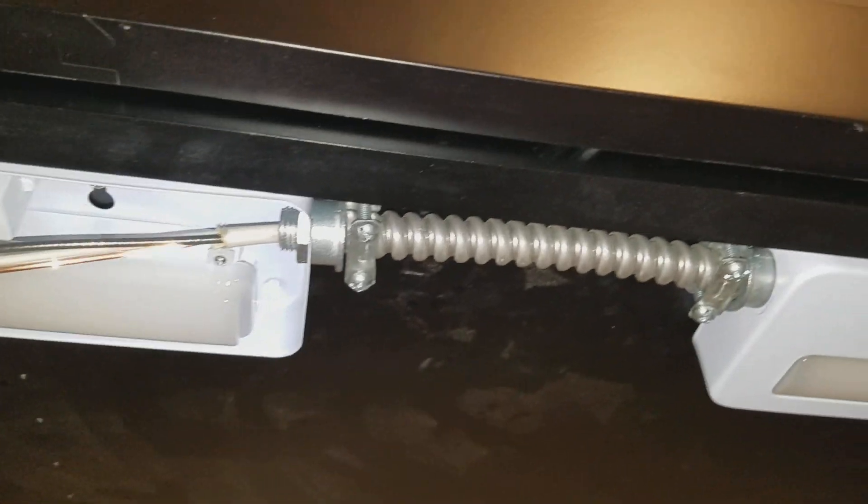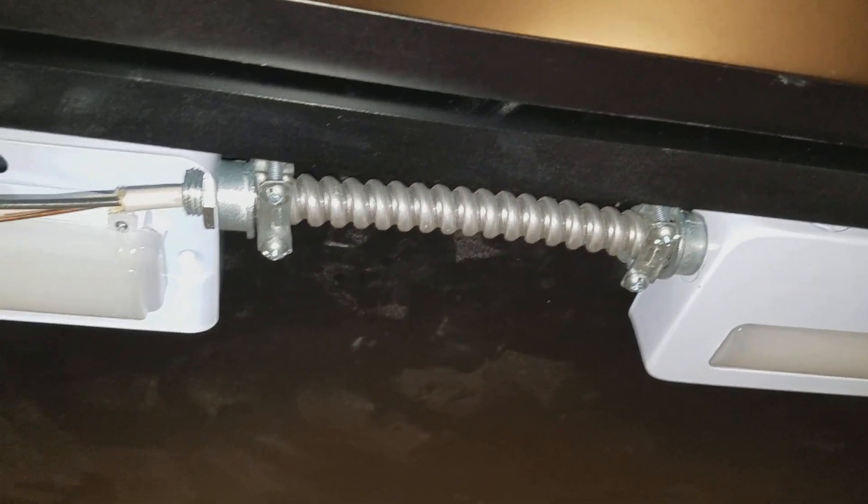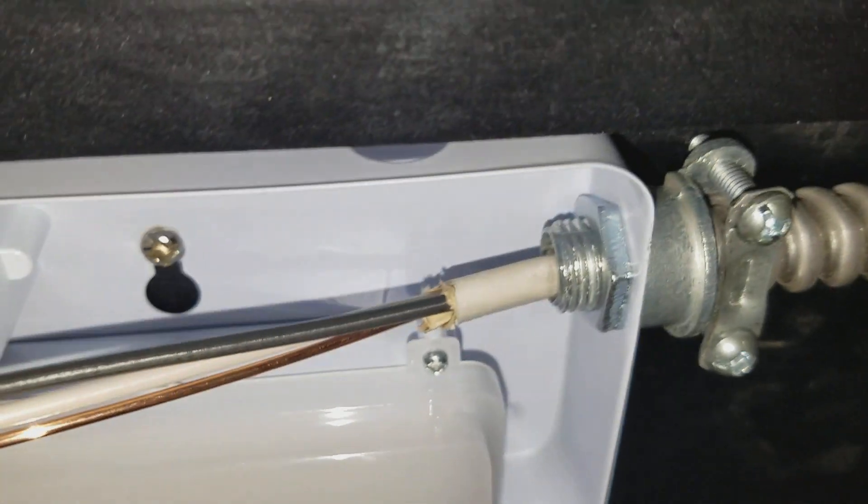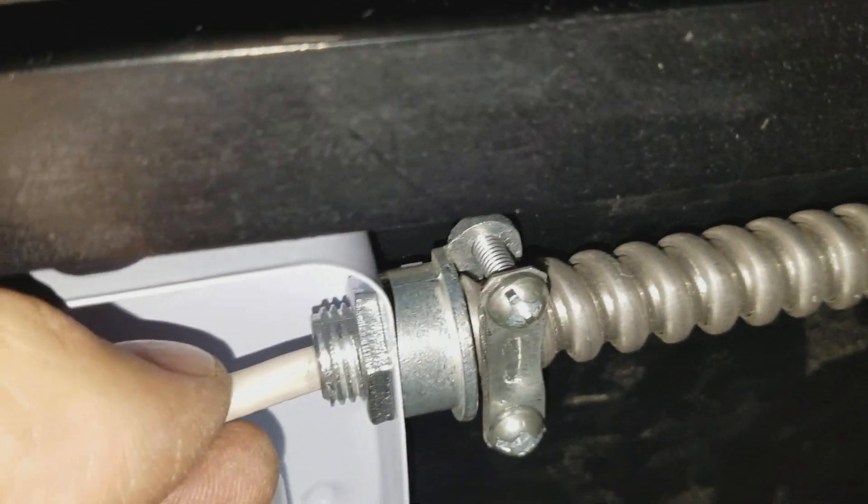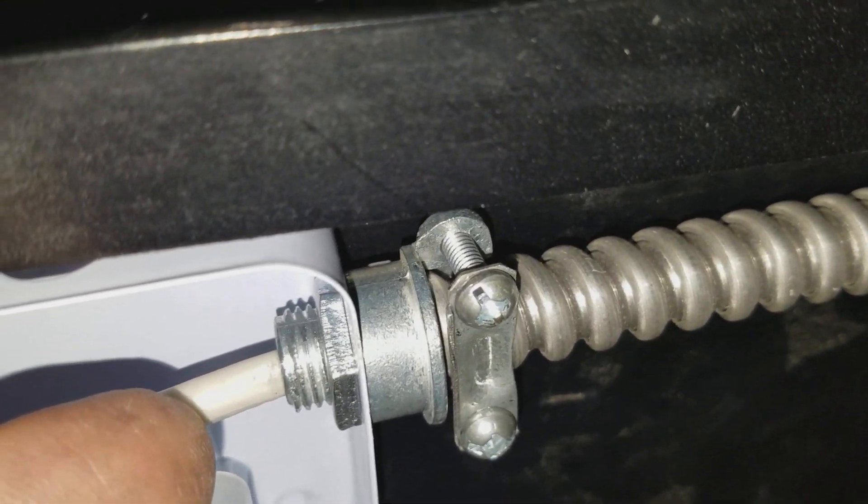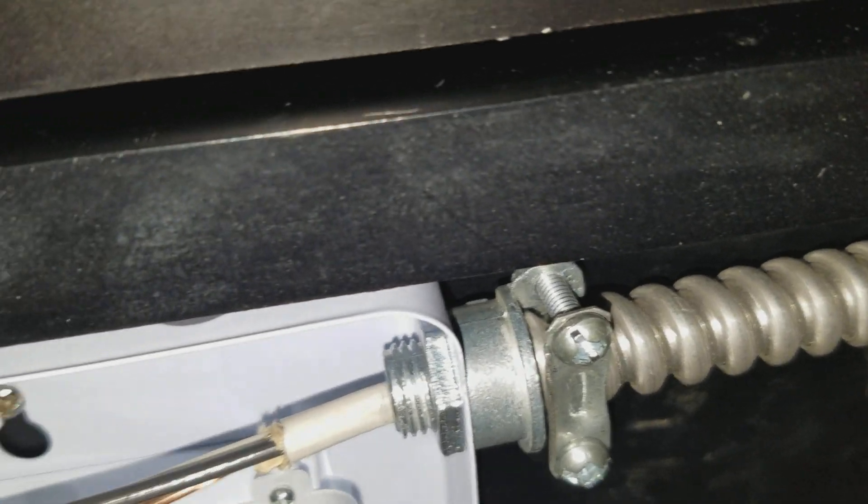So these lights here come with knockouts on the lights to connect them. And we are connecting them with a conduit. And inside the conduit is the 14 gauge wire that goes between them. We leave the non-metallic sheathing on the wire going through the conduit between light fixtures.